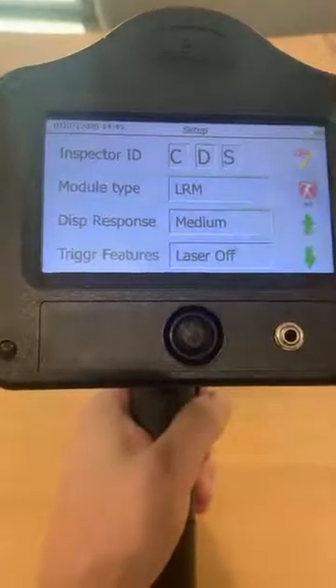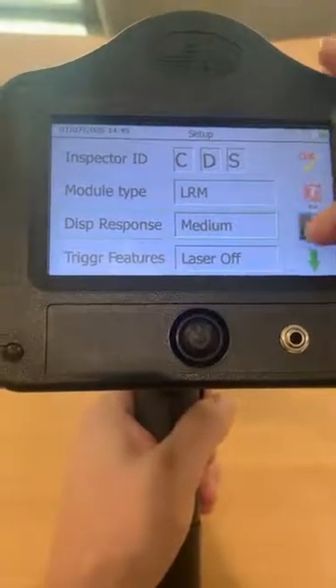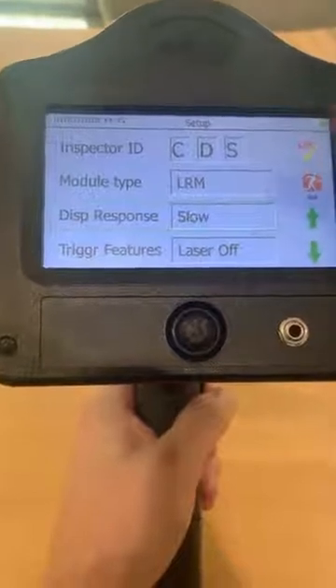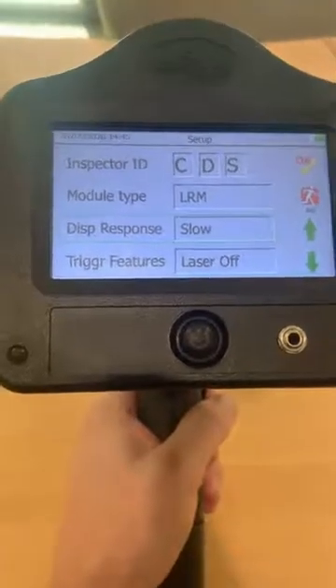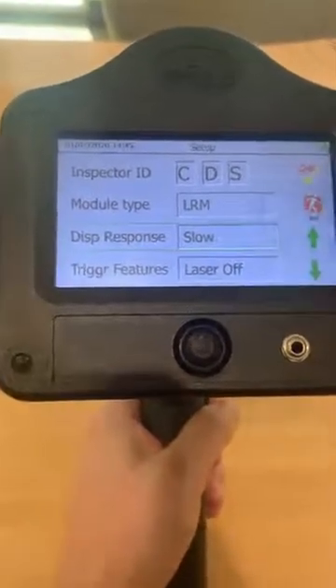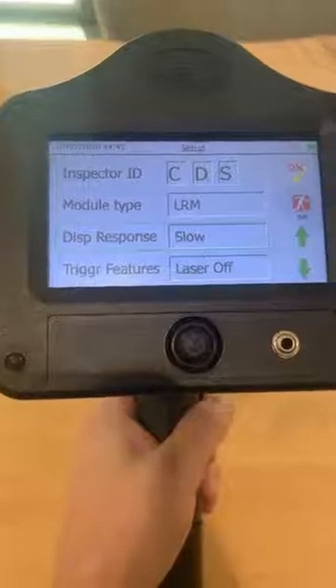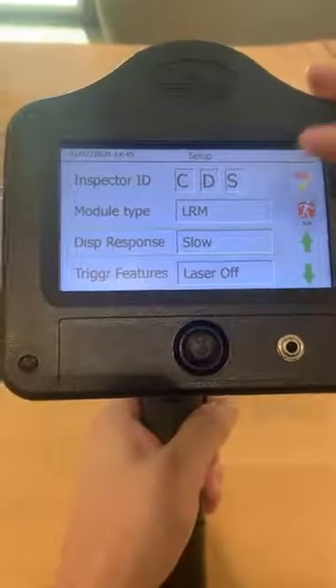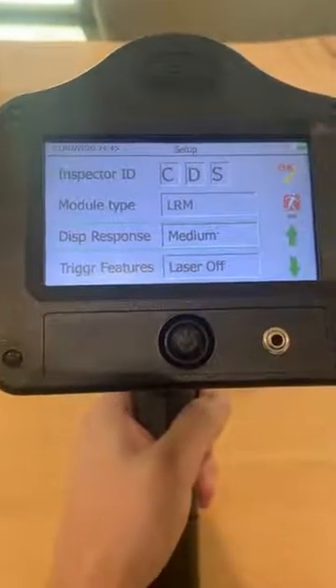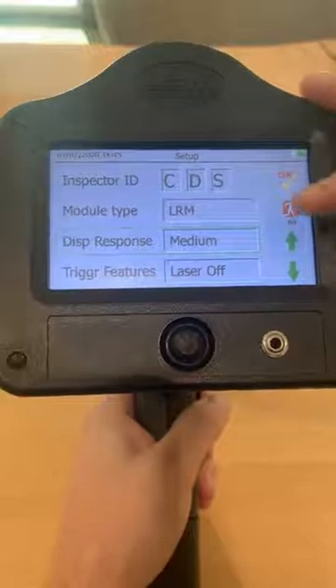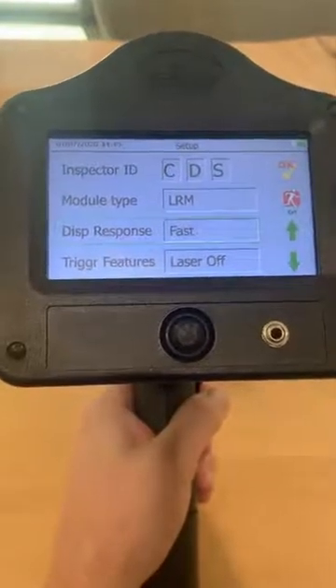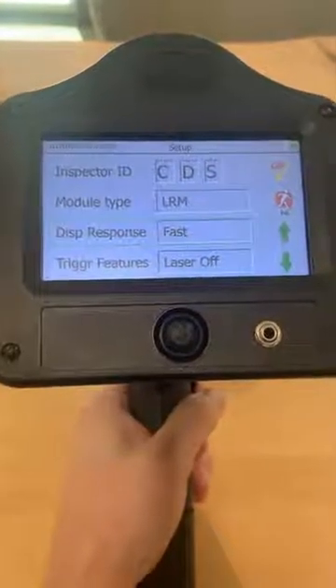For display response, we have slow, medium, and fast. This is more for the bearing applications. Slow is going to be for slow speed bearings, medium for pretty much all bearings, and fast for possibly VFD bearings.